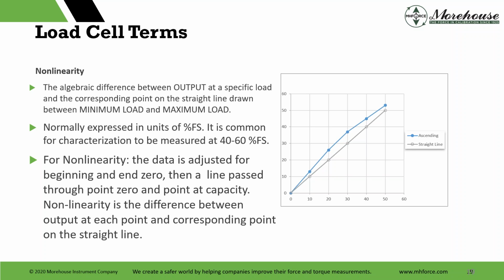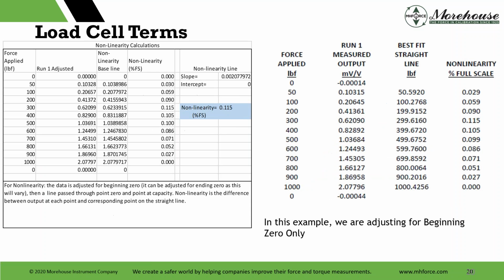The first one is non-linearity, which is the algebraic difference between the output at a specified load and the corresponding point on a straight line drawn between minimum load and maximum load. This is normally expressed in units of full scale. It's common for characterization to be measured at 40 to 60%. That's what you would see on a manufacturer's spec sheet. When it says non-linearity of 0.03, it's captured somewhere between that 40 and 60%. And for non-linearity, the data is adjusted for beginning and end zero, which we're reducing both. Then the line is passed through point zero and point at capacity. Non-linearity is the difference between the output at each point and the corresponding point on the straight line.